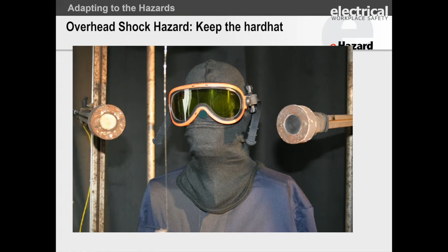Hard hats and safety glasses have been arc tested. They're not arc rated, they're not required to be, and most of them have not been arc rated. They may not provide all the protection you would possibly need, but they're not going to ignite, melt easily, and catch on fire. Every brand I've ever put in the arc is good up to around 40, 50 cals before they start to melt catastrophically. So it's really important to wear your hard hats and safety glasses - they really do save so much of your body, specifically if the parts are covered.